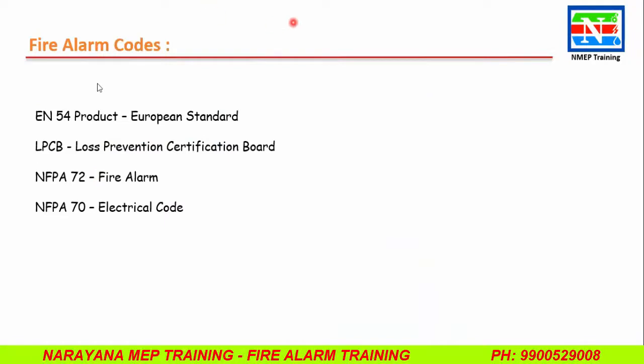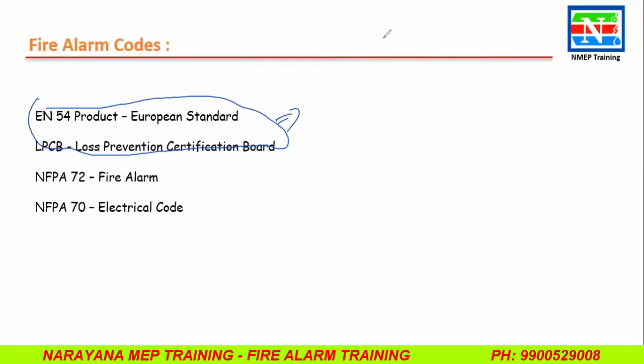Second, what are the codes and standards we follow for designing fire alarm? There are basically four codes we follow. Two are NFPA codes. The top two are with respect to the product — we should use UL-listed products or EN 54 products, and it should have an LPC — Loss Prevention Certificate. NFPA 72 is the fire alarm code, and NFPA 70 is the electrical code. These are the two codes we follow for designing.